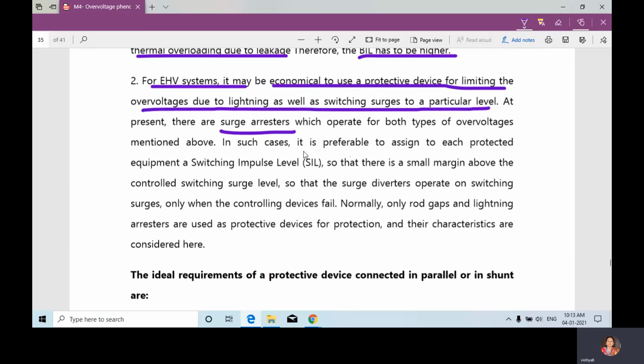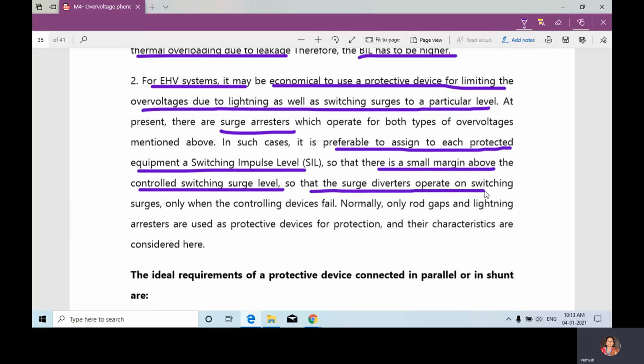Okay, in such cases, it is preferable to assign to each protective equipment a switching impulse level, that is SIL, so that there is a small margin above the controlled switching surge level, so that the surge diverters operate on switching surges only when the control devices fail. They are saying there is a small margin above the control switching surge level, so that surge diverters will operate on switching surges only when the control devices fail. Okay, if any control devices fail, then only surge diverters will operate.